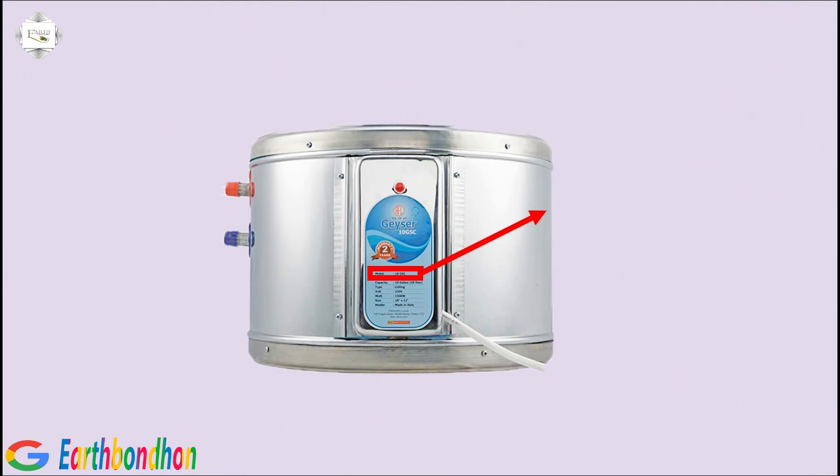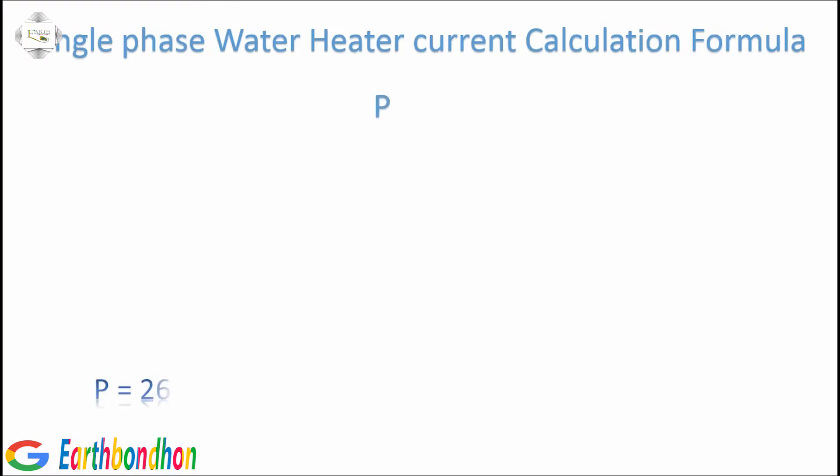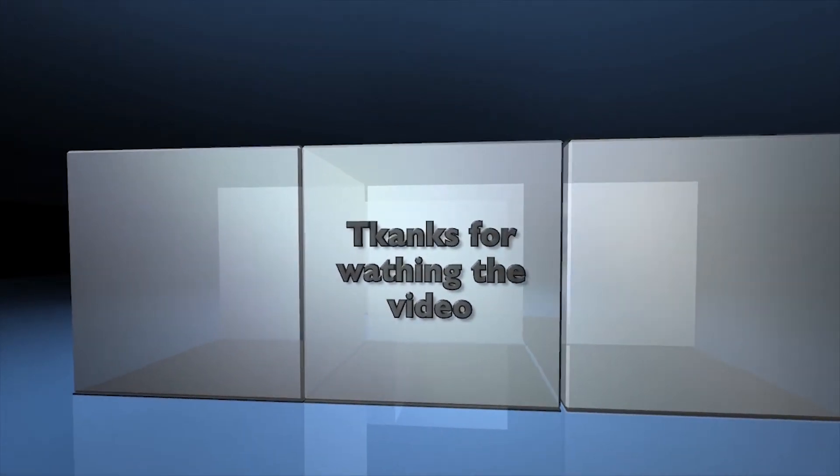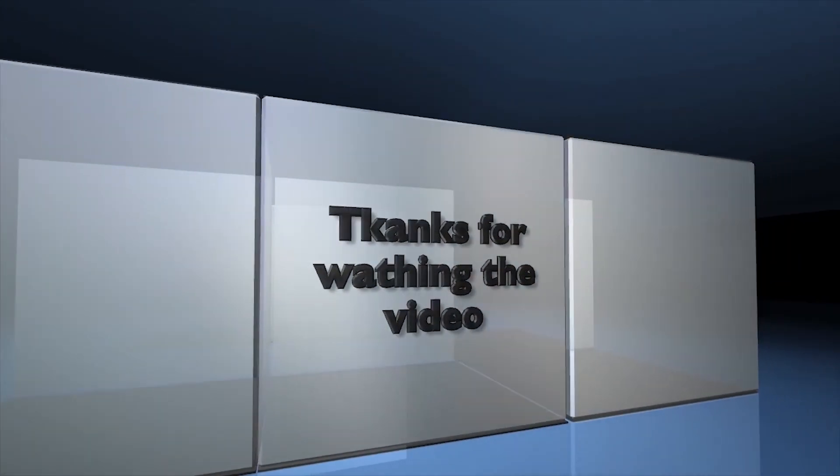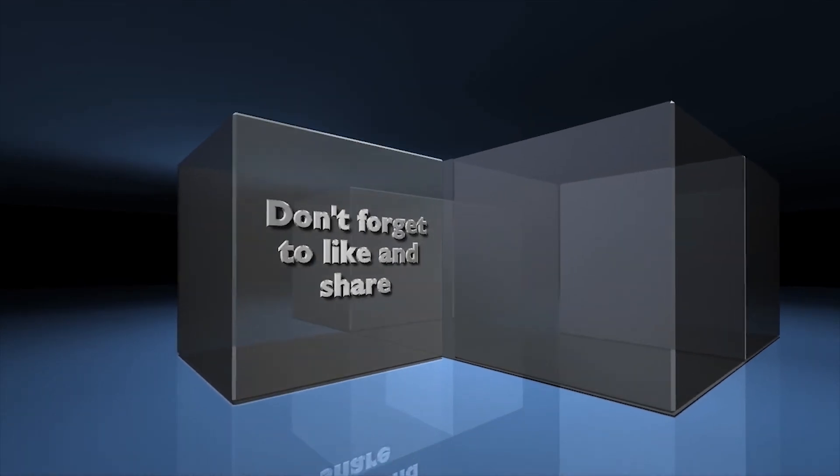Voltage equals 240 volts, power equals 2650 watts. I equals power divided by voltage. I equals 2650 watts divided by 240 volts. I equals 11.04 amperes load fuse. Thanks for watching the video.